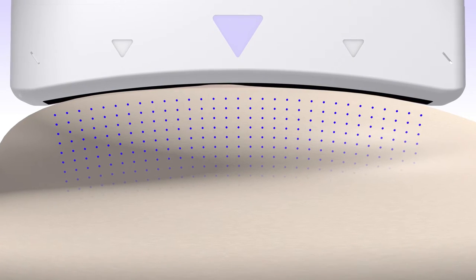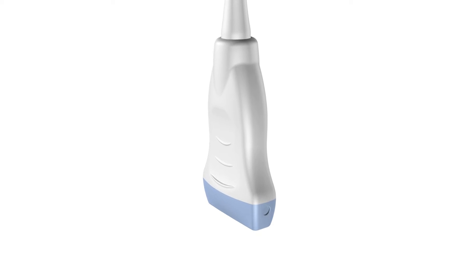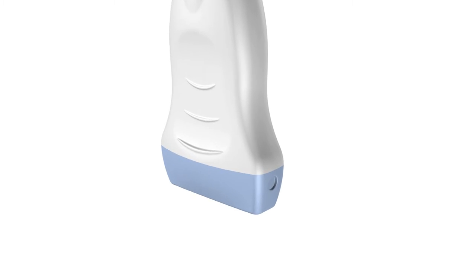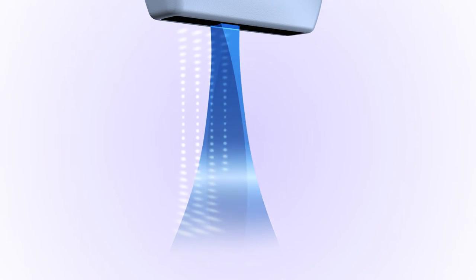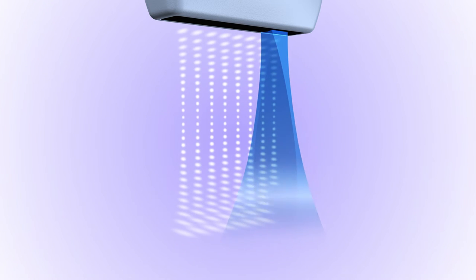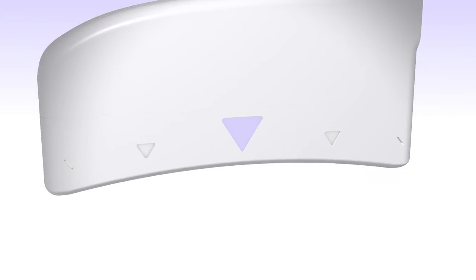Traditional handheld ultrasound is operator-dependent with long acquisition times and is limited to areas of focus known as focal zones. Areas outside the focal zone have decreased resolution. Increasing focal zones may increase resolution, but decreases frame rate.